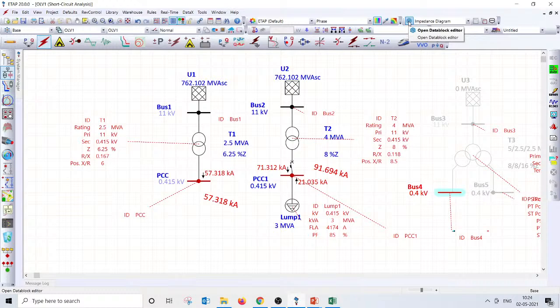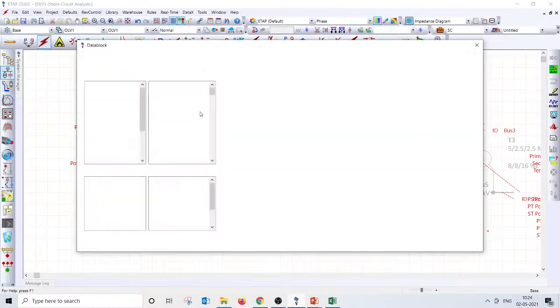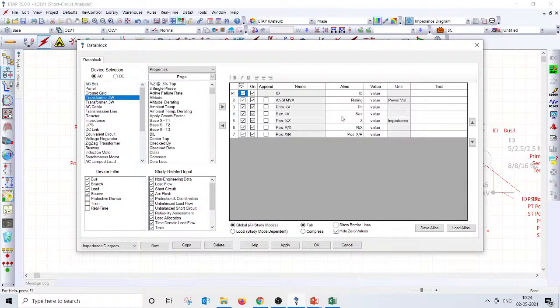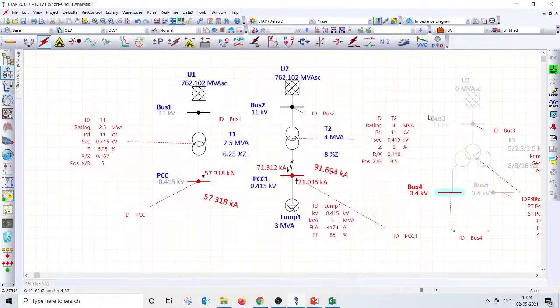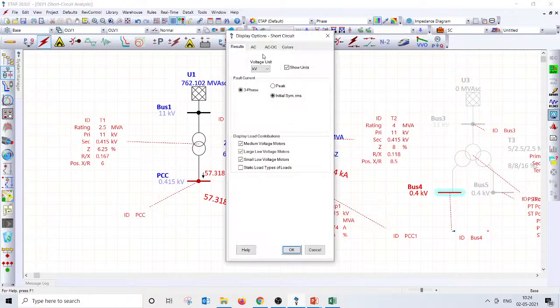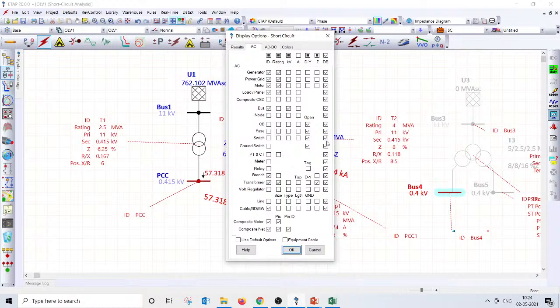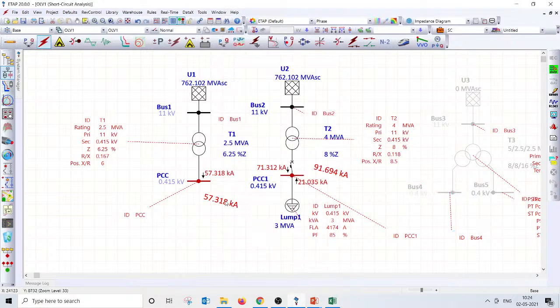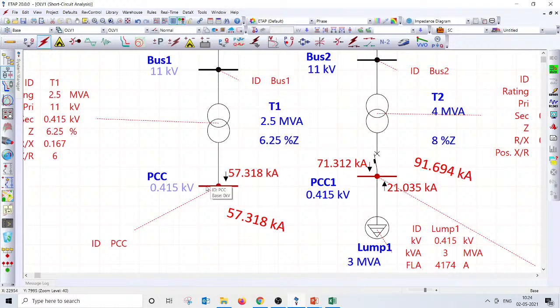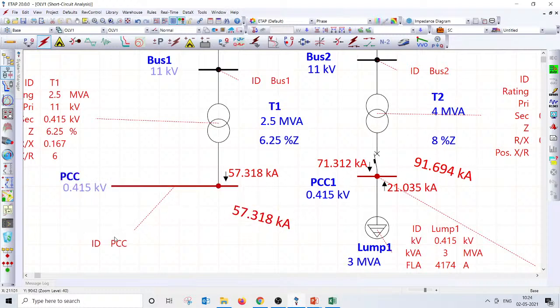Here is the data block editor. For enabling the data block editor, you need to select the equipment, the parameter to be displayed and for what studies, and switch it on or off here. If you want to connect it with a line, you can do that too. And for that you need to ensure that the DB data block option is checked here. I guess that ETAP tip is useful. Right, so now what we found is 57 kiloamps here is the fault current, and here it is 91 kiloamps, and here I have not really connected any loads. If I connect the loads, then the fault current could be more.